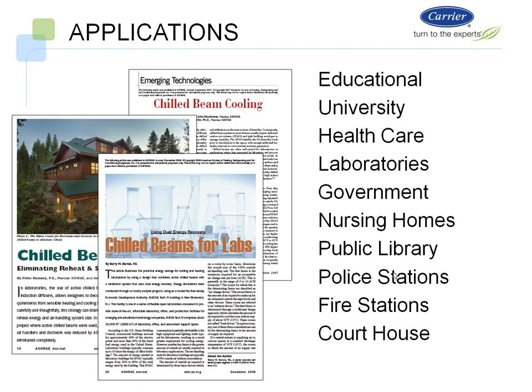Multiple applications for these, especially when you start looking at an induction type beam and being able to handle cooler water or doing latent with the beam itself as well. It's not just typically the university labs, but now you can start looking at more education buildings, healthcare, labs, government, nursing, public library, police stations, and fire stations. Think about this. We put public library in there. You would never do a library or museum type with a traditional chilled beam building, right? Where now you can do that, and it has been done.